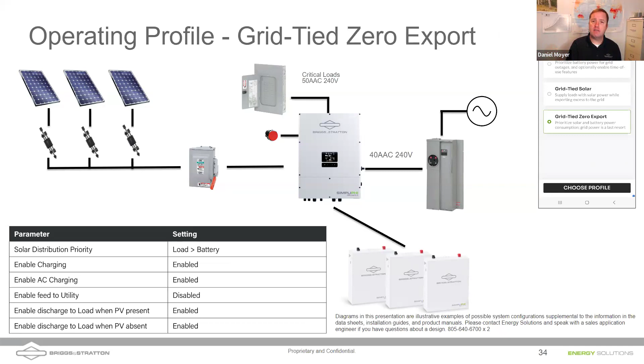The Sol-Ark 15K has a 200 amp pass-through, so we're not really doing backed up loads. We're essentially just keeping all the loads over here in the main distribution panel, feeding 200 amps right into the Sol-Ark, 200 amps right out. If for whatever reason the grid goes down, the Sol-Ark will disconnect itself from grid, run on batteries, solar, and potentially even a generator to off-grid the home. You could program the solar to essentially do everything in its power to not backfeed the grid and not consume from the grid, and only in extreme winters and at night do you want to buy from the grid.